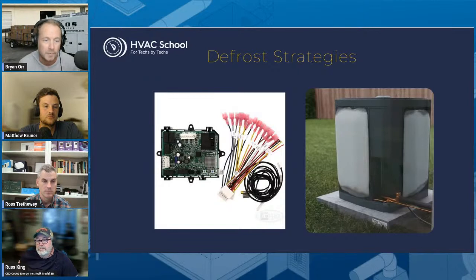So only when the equipment is actually being impacted by ice buildup are we defrosting, versus doing an old school time and temperature method where you're kind of defrosting because you think you might need to, not because you necessarily know you do. And that also saves a lot of energy, because every time we're defrosting, we're taking that heat pump and slapping it back in cool mode to get the ice off, which is a super inefficient way of doing that. But it's the only way that we have at our disposal on heat pumps.